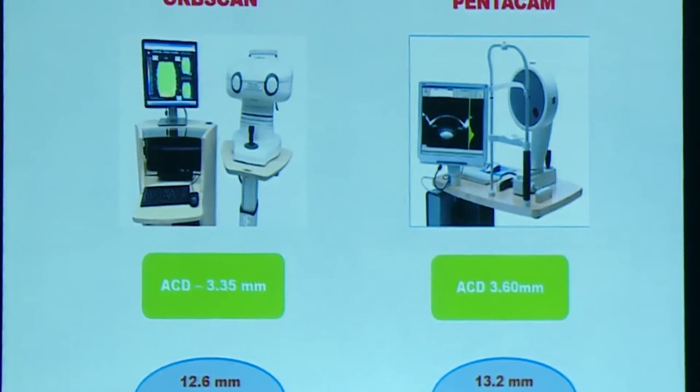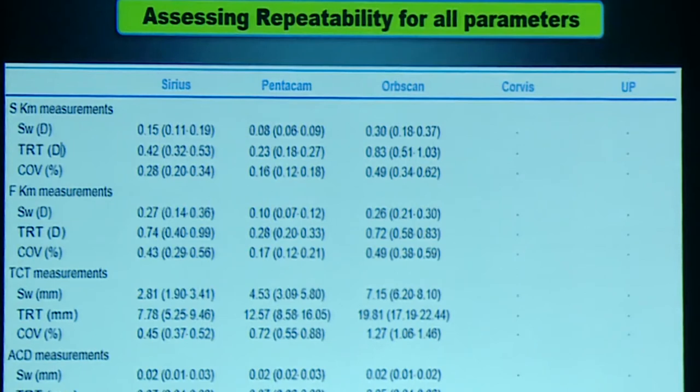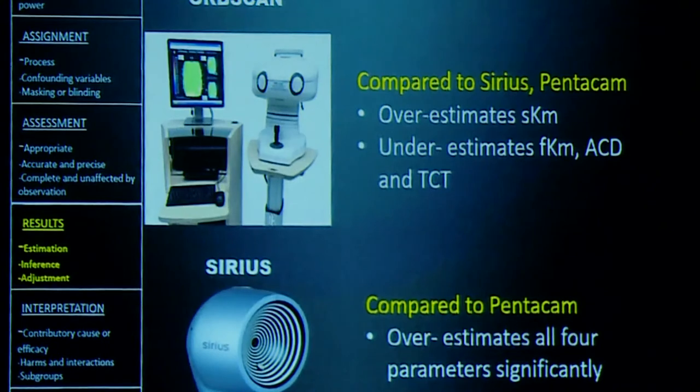We have published papers comparing five devices — Pentacam, Orbscan, Sirius, Corvis, and ultrasonic pachymetry — for repeatability of keratometry and AC depth. Looking at the results, Orbscan has the least repeatability for all measurements including keratometry, AC depth, and corneal thickness — meaning it has the maximum variability on repeat measurement compared to Pentacam and Galilei in normal eyes. Orbscan tends to overestimate steep keratometry, underestimate flat keratometry, exaggerating the astigmatism, and also underestimates corneal thickness and AC depth.